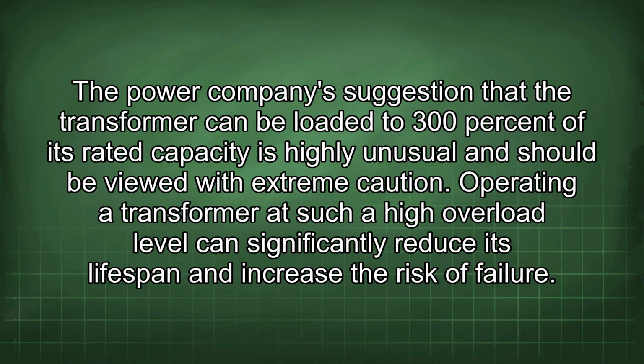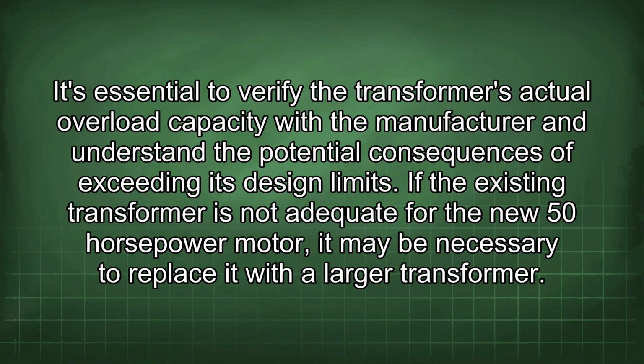The power company's suggestion that the transformer can be loaded to 300% of its rated capacity is highly unusual and should be viewed with extreme caution. Operating a transformer at such a high overload level can significantly reduce its lifespan and increase the risk of failure. It's essential to verify the transformer's actual overload capacity with the manufacturer and understand the potential consequences of exceeding its design limits. If the existing transformer is not adequate for the new 50 horsepower motor, it may be necessary to replace it with a larger transformer.